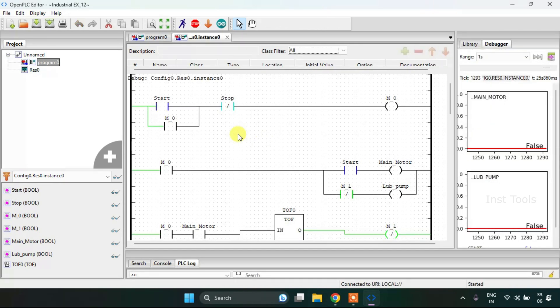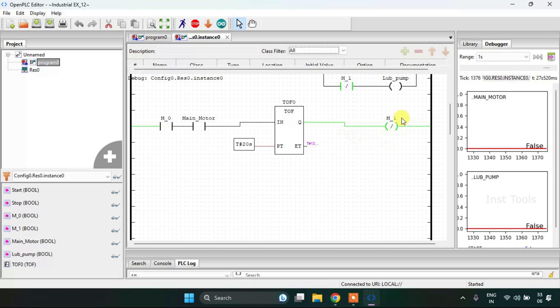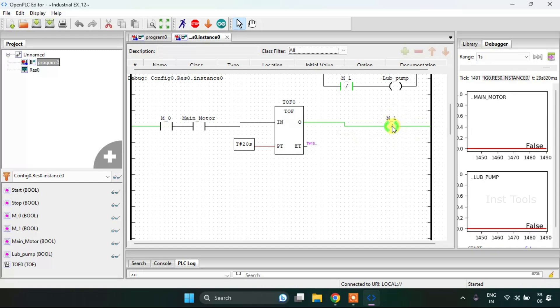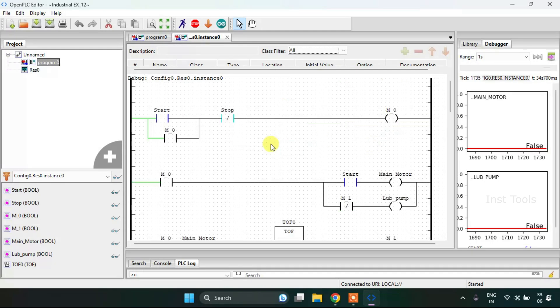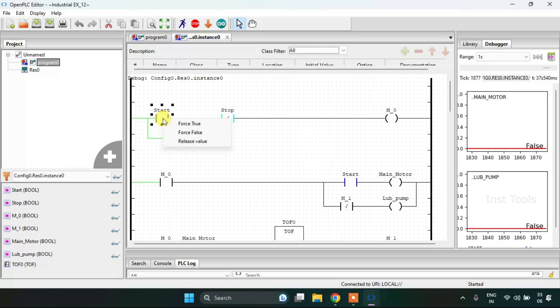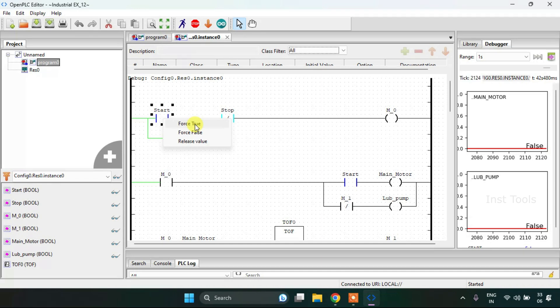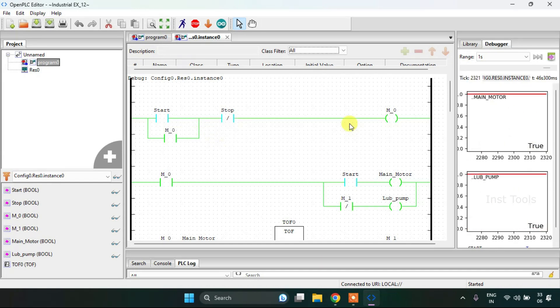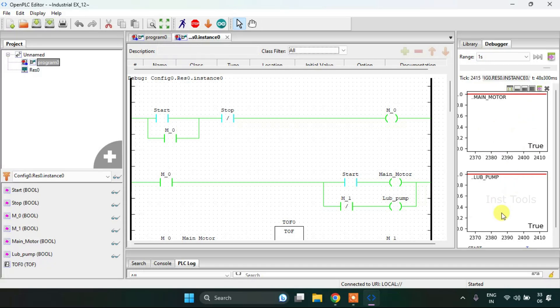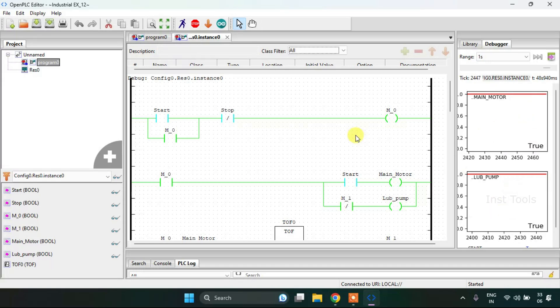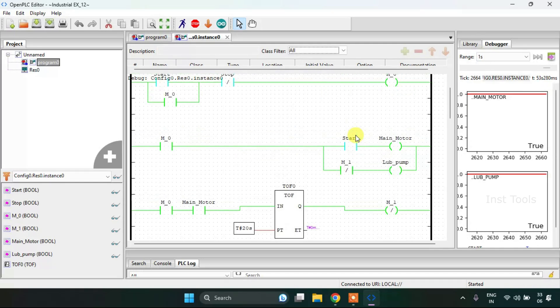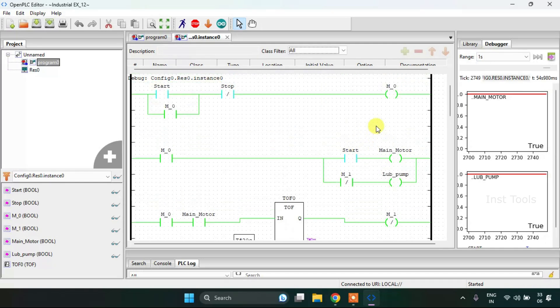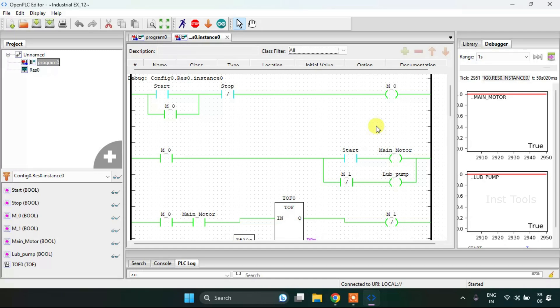I had forgotten to keep the M1 contact as negated. Now let me start the simulation again and force the start to true. As you can see, the main motor and the lubricating pump both are on at the same time.